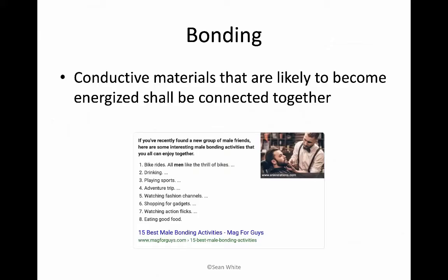And let's talk about bonding. Bonding is just connecting things together. Conductive materials that are likely to become energized shall be connected together. That's bonding. So you bond together your rails and you bond together the frames of your modules. Anything that you think might have a loose wire that could touch it, you bond it. You bond all the metal together.